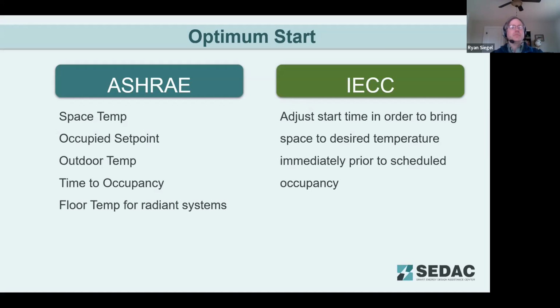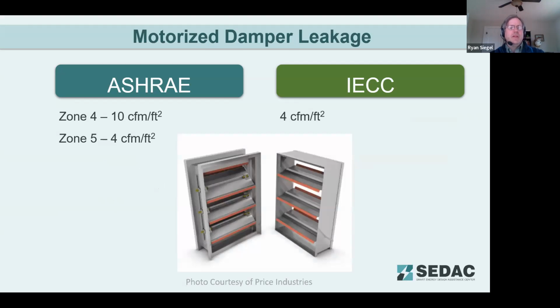Optimum start. ASHRAE gives you a few different methods for this, understanding that you'd have to monitor these things in order to provide that optimum start control, whereas the IECC is a little bit more vague and just says, hey, you need to be able to adjust that timing so that it's able to achieve the desired temperature by the time you schedule occupancy. So again, that's where ASHRAE, being a standard, is much more specific about what you need to measure such that the system has the ability to achieve the desired result. IECC just says here's the desired result, figure out how to do it. So as you're going through, it may be very beneficial to understand ASHRAE 90.1 and IECC. Even if you're using IECC as the compliance path, ASHRAE can give you some clues as far as how to achieve that.